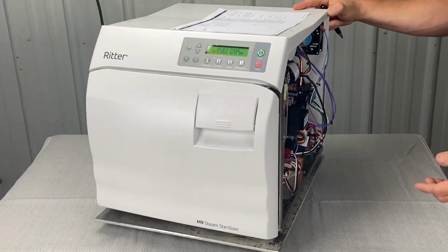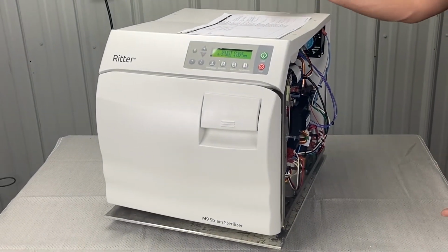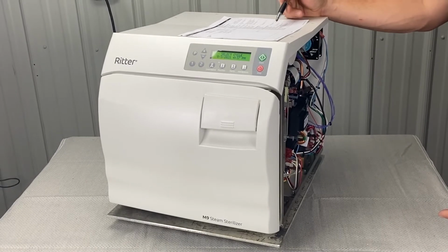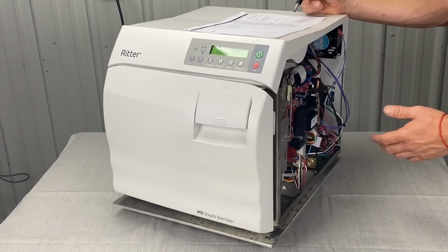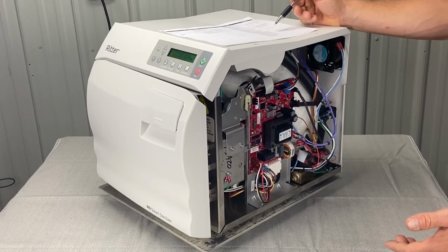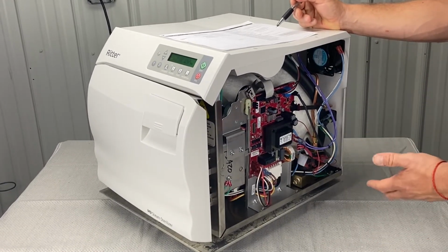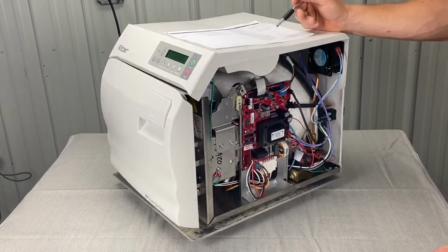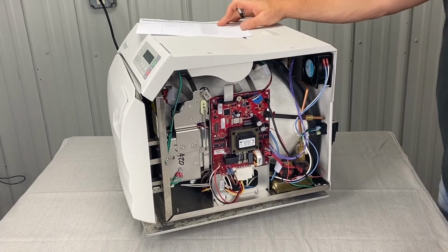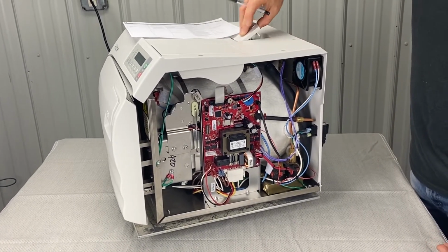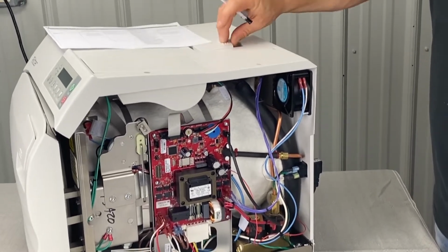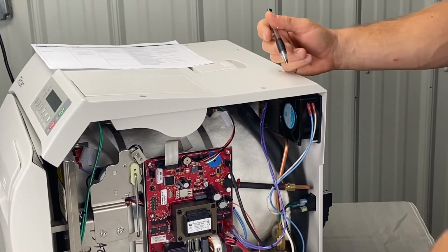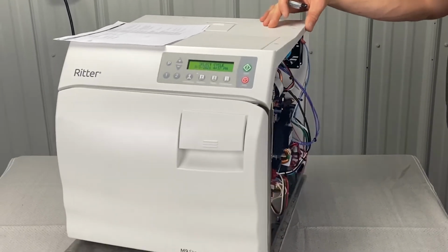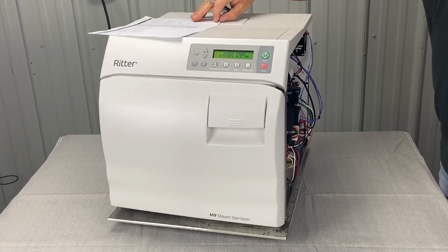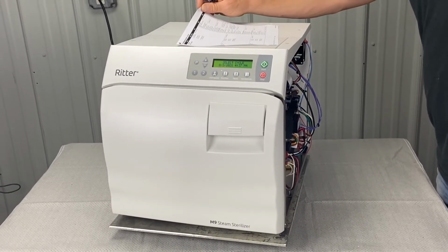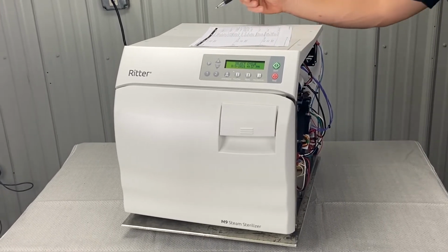That could be it. So, door gasket, we checked. The rectifiers, we just talked about. Fill and vent valve solenoid, we talked about as well. Leaking or defective air valve, that's the one back here. And then you also have the pressure relief valve, which is right here. If you pull on that, sometimes they stick open and they will leak out the bottom there. So we got C575, covered the pressure leaks. C575 continued. Okay, more pressure leaks.